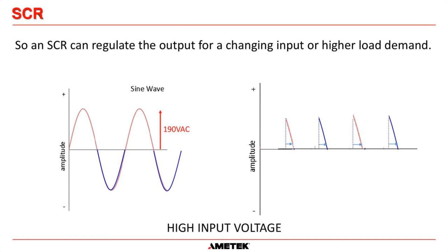That's why we use SCRs in our rectifier bridges, because we don't know—if we send a charger out, the nominal rating might be 480 volts 3-phase, but we don't know if your plant's voltage is exactly 480. It could be 500, it could be 460—they're all over the place depending on your transformer windings, how far the equipment is from the transformer, and whether it goes through an MCC. So we have to say, for a 60-cell battery, our charger will give you 135 volts DC out, and to do that we constantly turn these SCRs on at certain points in the waveform to maintain that 135 volts DC despite varying AC input voltages, within the parameters our rectifiers will accept.